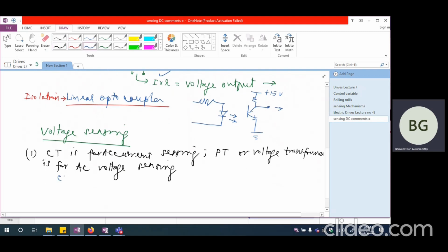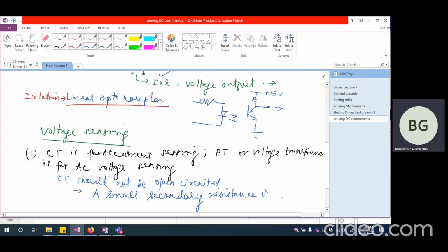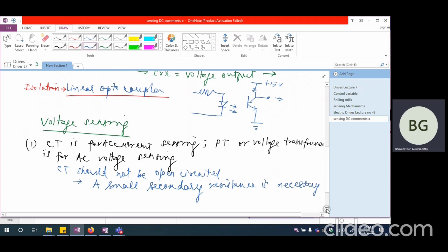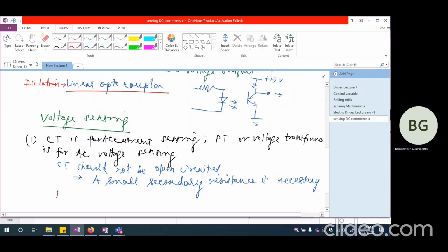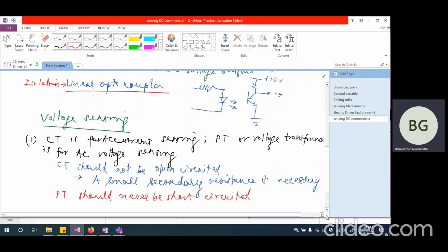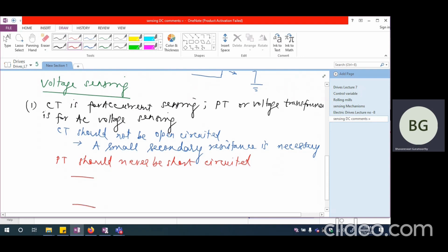We said that a CT should not be open circuited. It should always be connected with a small resistance. So a small secondary resistance is always necessary. This is what we said in the case of CT. The same way, in PT, the potential transformer should never be short circuited. Because if you look at the PT, generally what happens is, if I want to measure the voltage across two terminals, these are the terminals from which I want to measure the voltage. So this is the voltage to be measured.